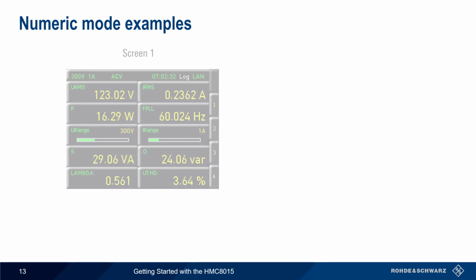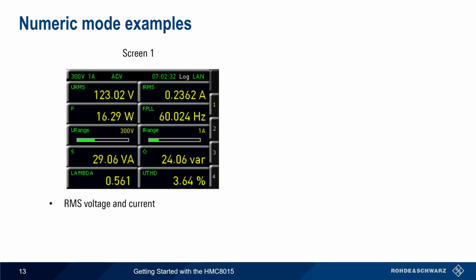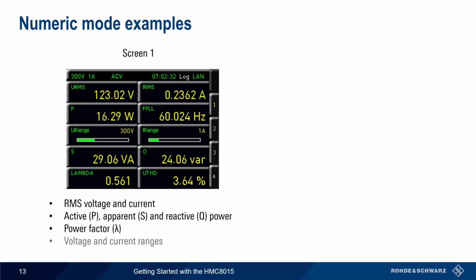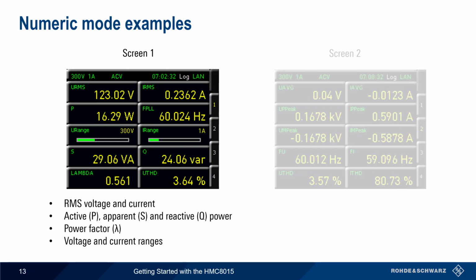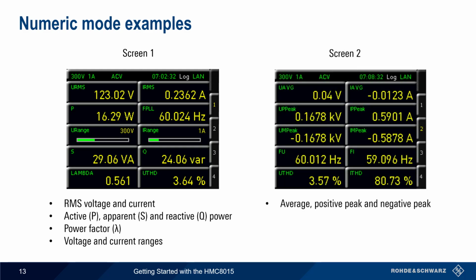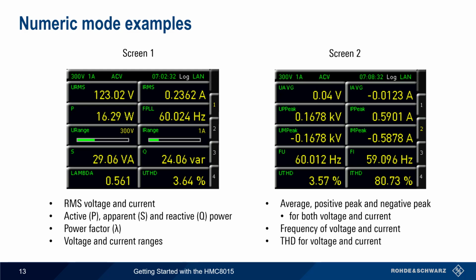Let's look at some of the numeric mode measurements. On the first screen, we have the instantaneous RMS values of voltage and current, as well as active, apparent, and reactive power and power factor. The voltage and current ranges, here 300 volts and 1 amp, are displayed as bar charts showing the instantaneous values as a function of range. On screen 2, we have the average, positive peak, and negative peak values for both voltage and current, the frequency of voltage and current, and the total harmonic distortion of voltage and current.